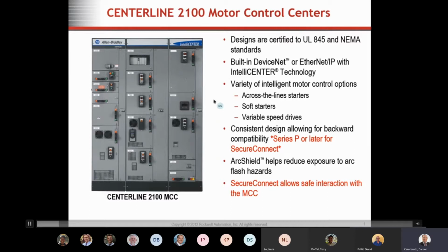So if I go to the onset of the MCC with intelligence, that was DeviceNet back in the day. Now everything's pretty much Ethernet, so you'll see IntelliCenter technology throughout the slideshow, meaning an Ethernet backbone for all the intelligent devices across the line starters, soft starts, variable speed drives, and so on. This is a pretty consistent design going back to the early 70s, but please be aware the SecureConnect is only compatible with Series P or later. That's one of the gotchas, I want to caution you with that. If you need an exact serial number and date, please give me the nameplate value off your MCC and we'll make sure it's compatible.